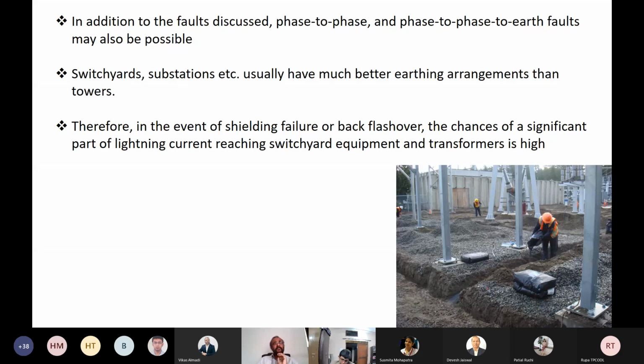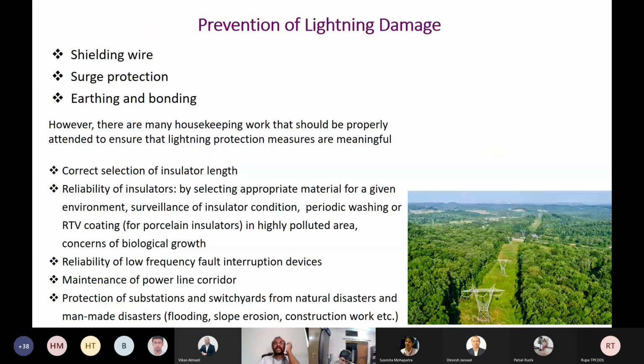Most often towers, even medium voltage towers, may be placed at locations where the tower footing resistance cannot be taken below a certain value. But usually when you are implementing a transformer or switchyard, then you select a place where you can reduce the earth resistance, so that in these places the earth resistance is much less compared to that of towers. Therefore, in the event of shielding failure or backflashover, the chances of a significant part of the lightning current reaching switchyard equipment and transformers is high. So that is why usually we are more concerned about the protection of substations when it comes to lightning scenarios.